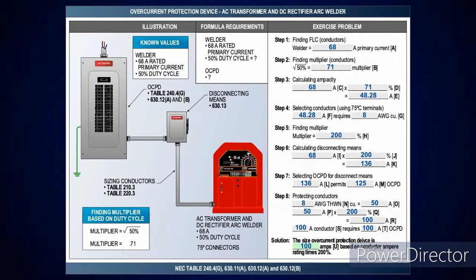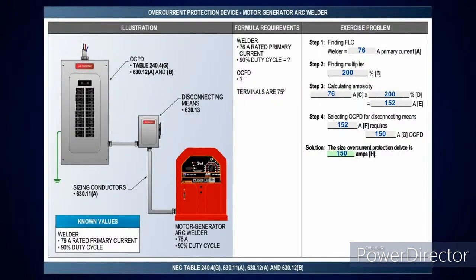Okay, either way is going to be correct, but here we're going to protect the conductors, and we did it based on the amperage of the conductors at 200%. Okay, now here's one where I'm just showing what I talked about. I'm just going to do it at 200% and size the overcurrent device. I'm not even going to do the amperage for the conductor or anything. So I have 76 amps, and I'm doing a motor generator type here, with a 90% duty cycle. So I look in the left-hand column at 630.11(A), pick up 90%, come across, and it tells you take it at 200%.